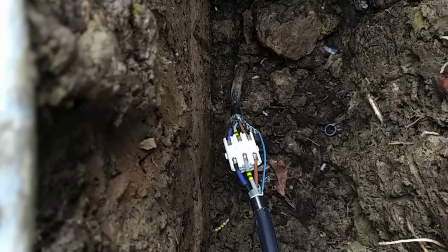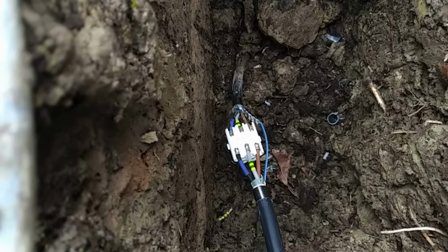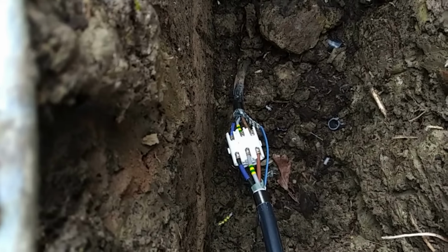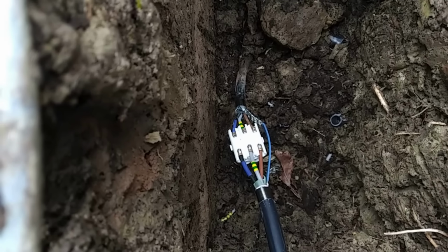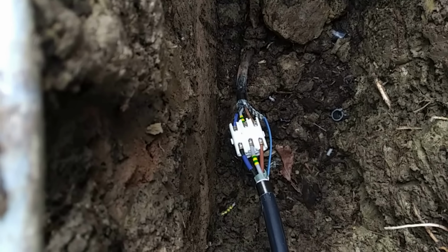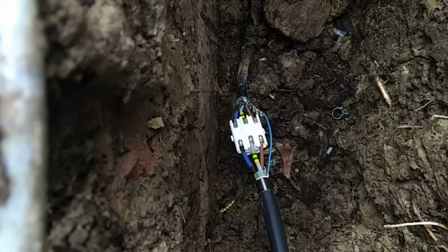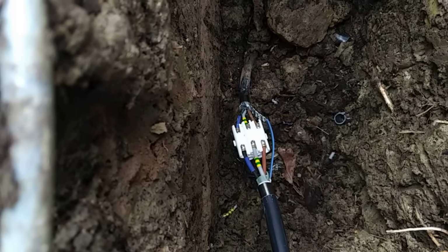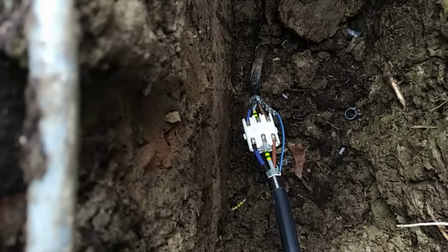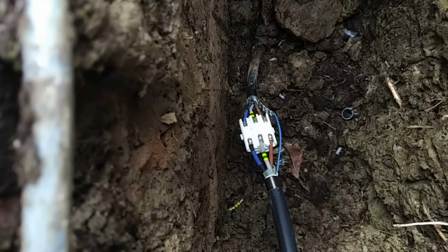It certainly hasn't got any British Standard 5733 markings on it, but it's okay here because this is in effect a temporary repair. We will hopefully be coming back to sort this out properly. What we're doing today is just to get the hot tub back in action and to remove the fault, but really this needs some proper long-term TLC on all the garden electrics here. But if it were a joint that I was putting in the ground to be permanently buried, I think I'd still prefer the resin joint kit rather than this whisker affair.